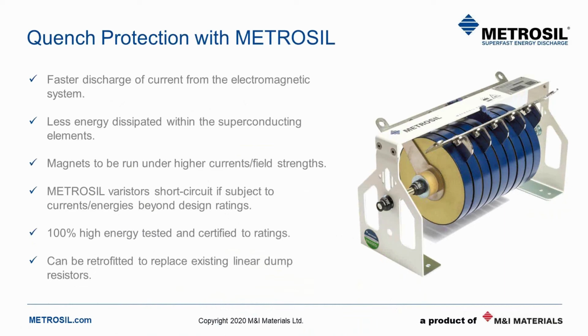That's really good. So to summarise, METROSILs are high energy varistors that are extensively used in the power industry to protect against transient overvoltages and to provide a means to quickly extract energy from inductive loads. Benefits of METROSIL over linear resistors, namely the faster discharge, the lower energy discharge in the coil, and the overvoltage protection aspect, are all applicable to superconducting magnet discharge during an unexpected quench.